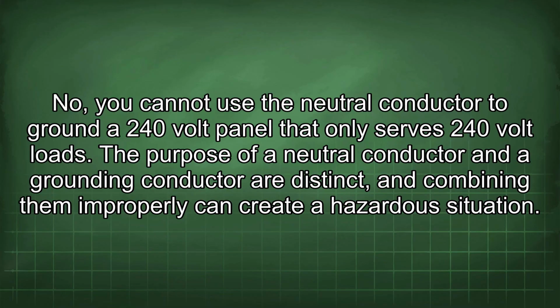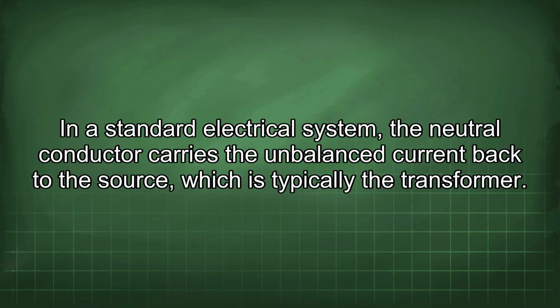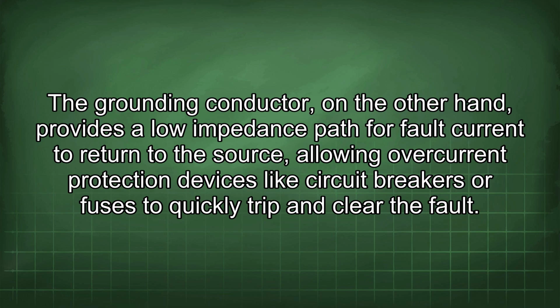No, you cannot use the neutral conductor to ground a 240-volt panel that only serves 240-volt loads. The purpose of a neutral conductor and a grounding conductor are distinct, and combining them improperly can create a hazardous situation. In a standard electrical system, the neutral conductor carries the unbalanced current back to the source, which is typically the transformer. The grounding conductor, on the other hand, provides a low impedance path for fault current to return to the source, allowing overcurrent protection devices like circuit breakers or fuses to quickly trip and clear the fault.